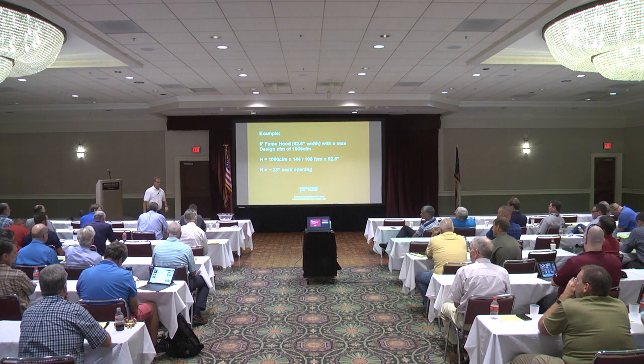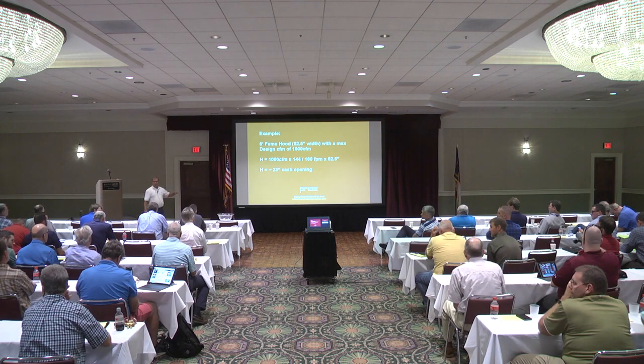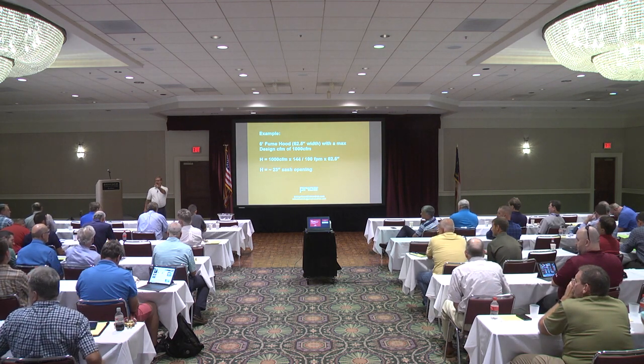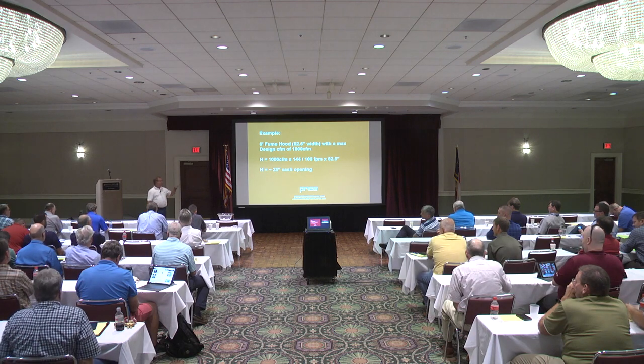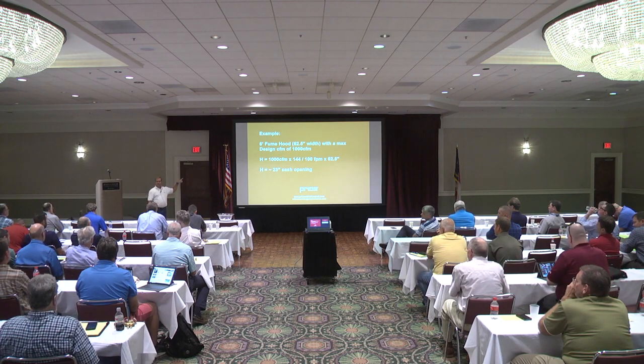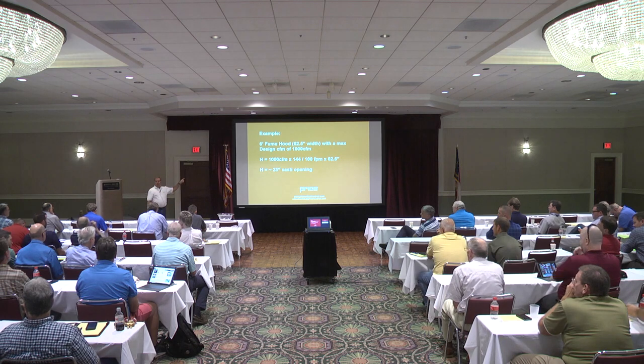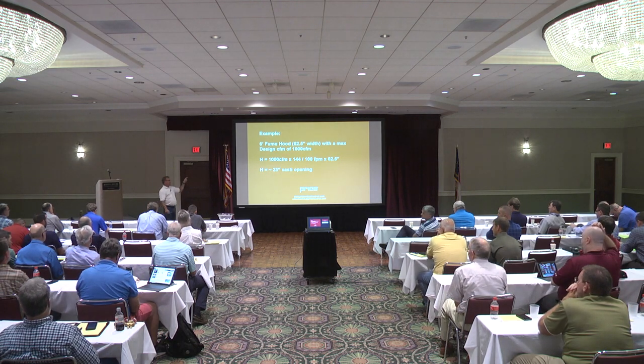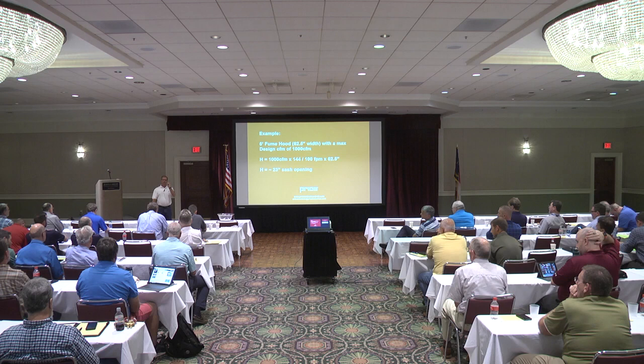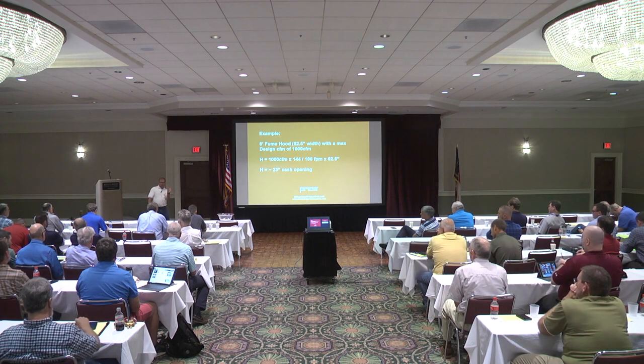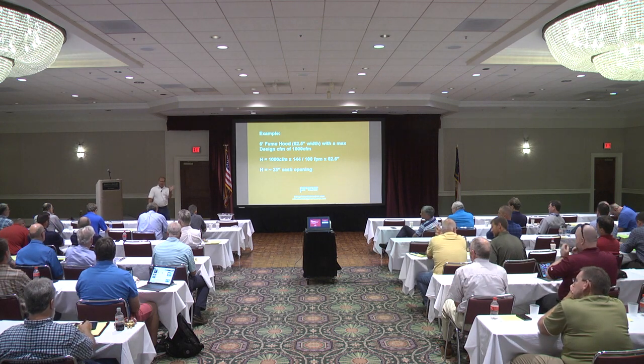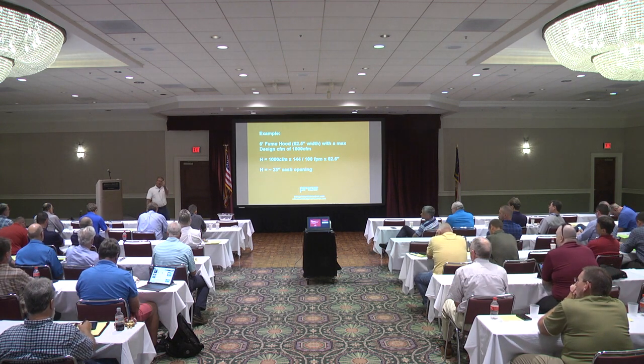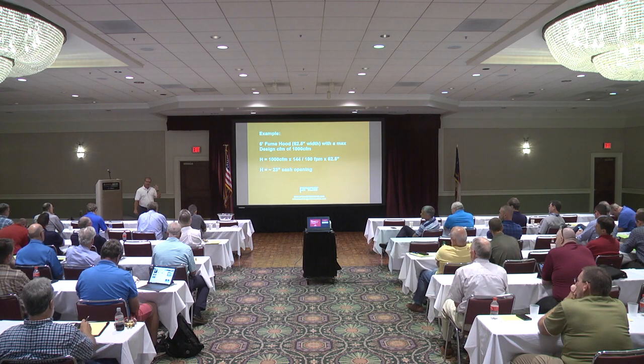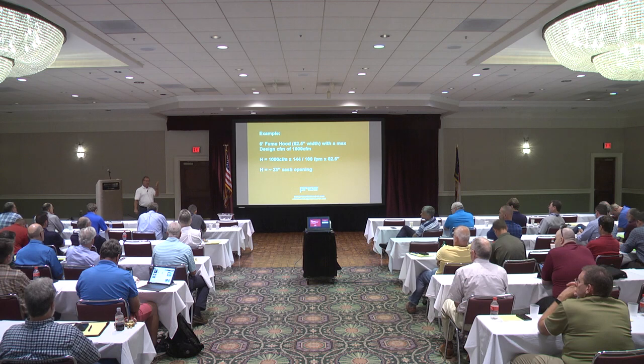So the only real way to do it is go up there and try to. Well, I'll give you that every day and twice on Sunday. Give me a traverse of 1,000 CFM. That's what I want. But the only way you're going to get to 1,000 CFM is if you raise that hood to 23 inches because it's a VAV hood. And a VAV hood has a velocity set point from the sash movement. So the velocity doesn't go up based on sash movement like a constant volume hood. It maintains 100 feet per minute as you change the sash position.